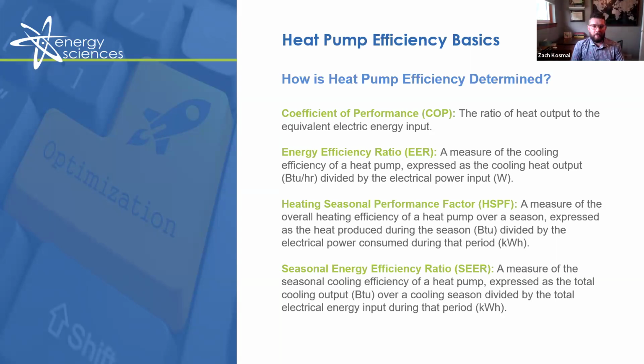And the simplest example of COP would be an electric coil or an electric heater, which has an efficiency of 100%, meaning your input energy equals your output energy. And that is a COP of 1, to set your baseline there. So just to give you some ranges of COPs for different types of heat pumps, an air source heat pump generally varies between 2.5 to 4 on the COP. A 4 COP, just a reminder, would be 1 unit of input energy equals 4 units of output energy.